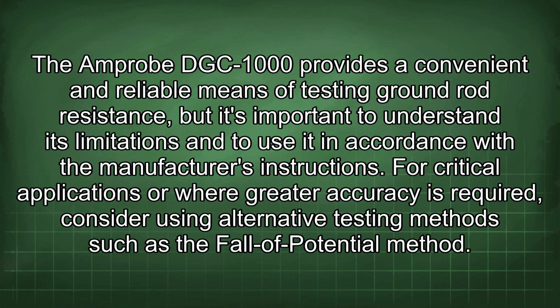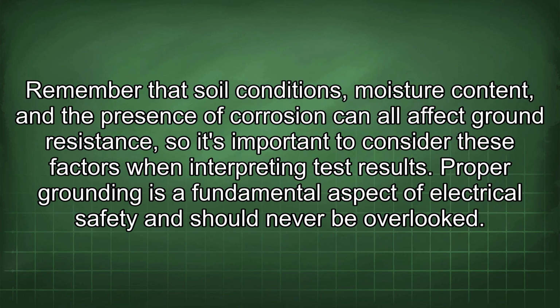For critical applications or where greater accuracy is required, consider using alternative testing methods such as the fall of potential method. Remember that soil conditions, moisture content, and the presence of corrosion can all affect ground resistance, so it's important to consider these factors when interpreting test results.